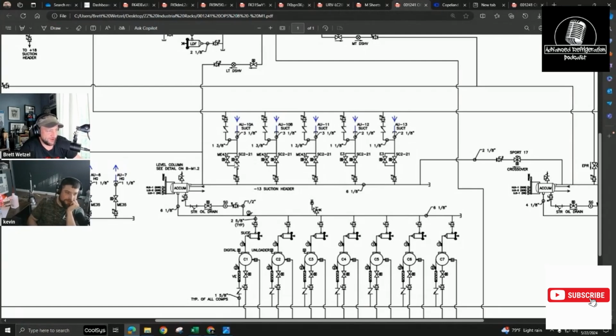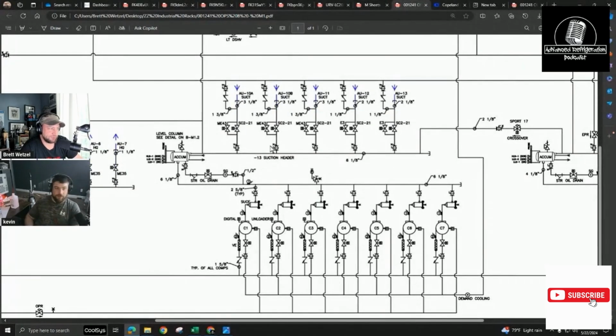That's like a 2 1/8 valve, isn't it? It's a big freaking rack. Yeah, that's your pump out. Costco's big on this with the older racks. The way it would work is when the circuit goes back into refrigeration, it energizes a time delay relay and the smaller solenoid. The normally closed of that time delay relay is wired to the small pump out solenoid. It's going to go for 5 to 7 minutes, longer the better, and pump out all that refrigerant in the coil. Then it's going to time out and bring on the refrigeration.